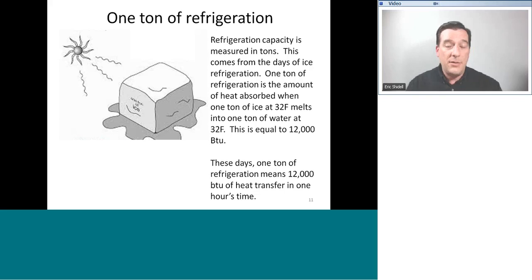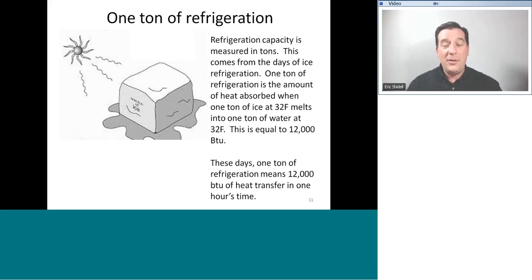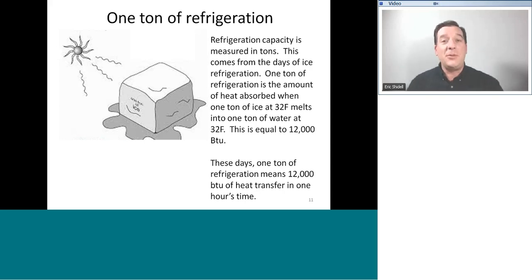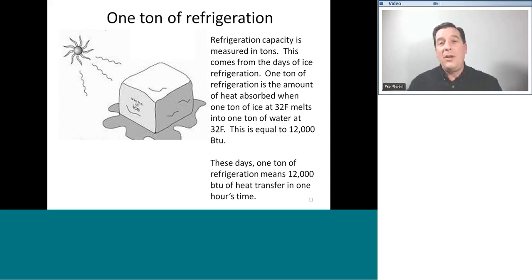When we talk about refrigeration, we talk about tons of refrigeration — a two-ton air conditioner, a five-ton air conditioner, a 20-ton air conditioner. When I first got started in HVAC, I didn't know the difference between a furnace and a water heater. I was talking to my dad one day and said I was servicing a two-ton air conditioner, and he said 'whoa, two tons — that must be a really big one,' thinking two tons meant 4,000 pounds. Refrigeration capacity is measured in tons, but this term comes from the days of ice refrigeration. It refers to the amount of heat energy absorbed by ice as it melts. One ton of refrigeration refers to the specific quantity of heat required to cause one ton of ice at 32 degrees Fahrenheit to completely transform into one ton of water at 32 degrees Fahrenheit.